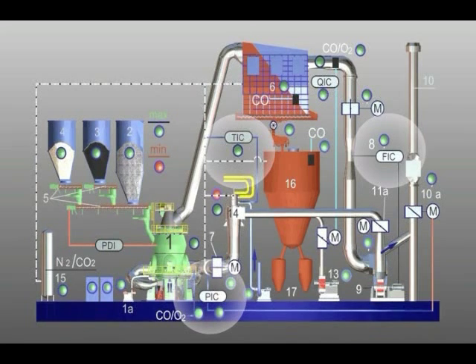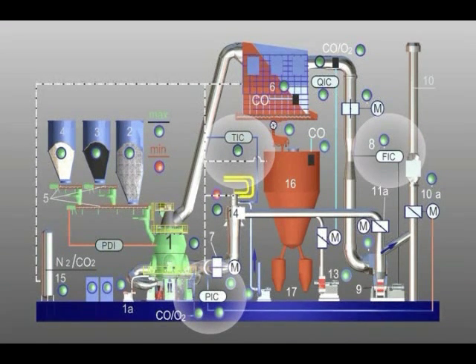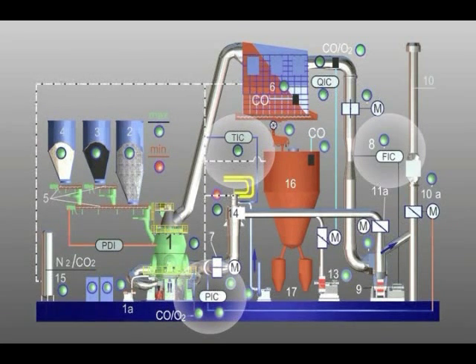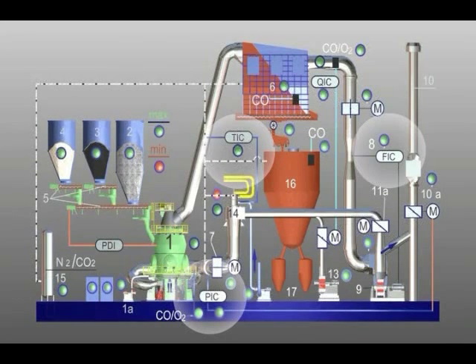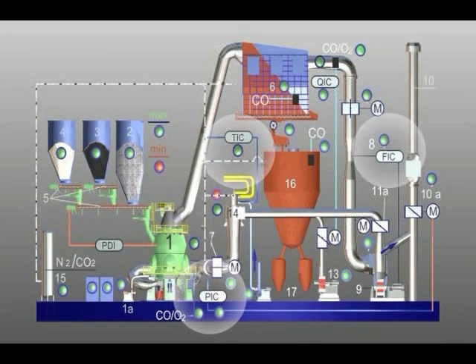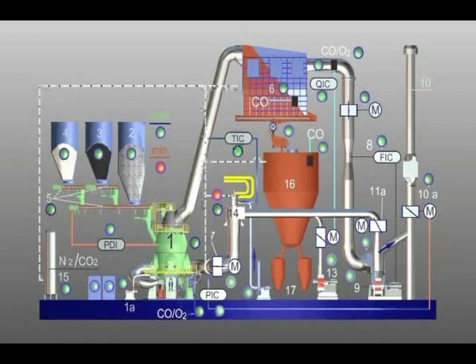Whilst the entire plant is warming up, the carbon monoxide oxygen analyzers are switched on. The controlled systems at this time are pressure measurement upstream of the mill, PIC, measurement of process volume flow, FIC, and temperature measurement downstream of the mill, TIC, during operation.